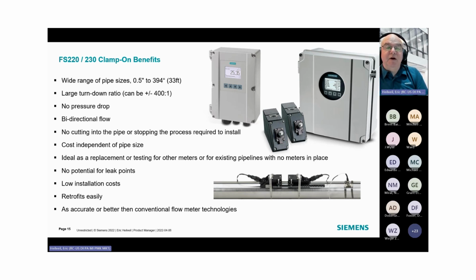All right, hang on. We've got more questions coming in. All right, I love these. Okay, so for gas applications, how do you compensate for temperature or pressure? Well, we compensate for temperature with an RTD. If it's a gas flow, there's an RTD that mounts, it's a clamp-on RTD instead of a thermowell, that mounts on the outside of the pipe and monitors the temperature of the pipe. And that allows us to correct for temperature variations within the pipe.